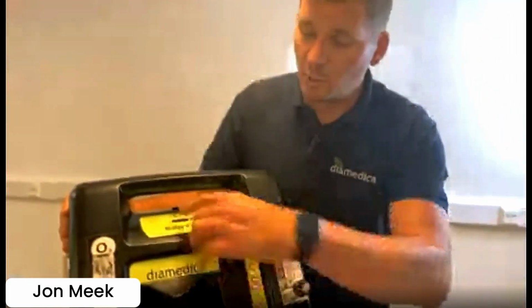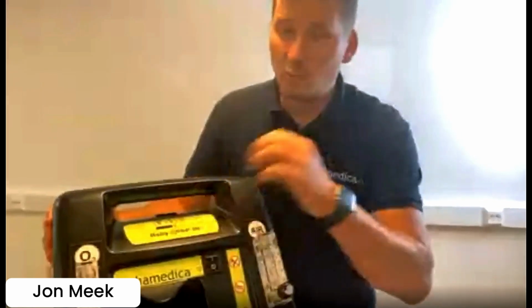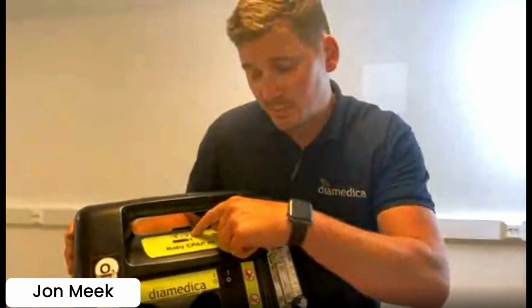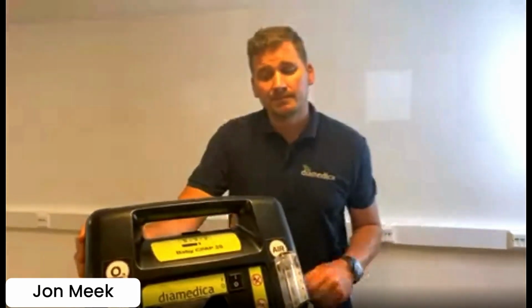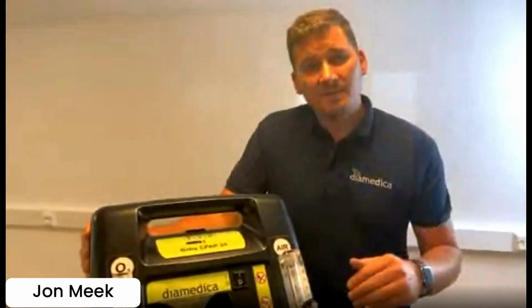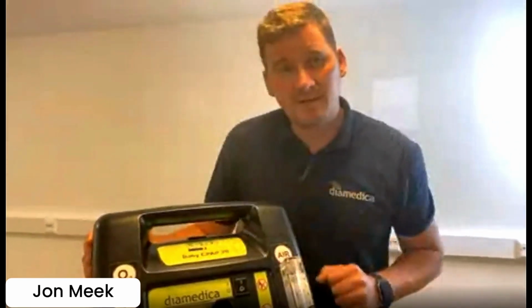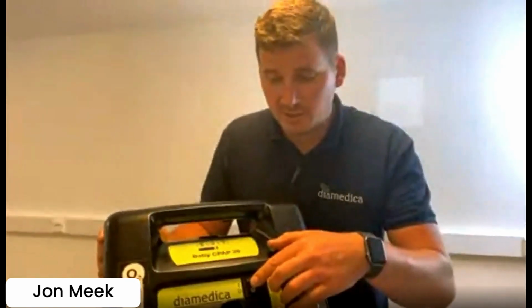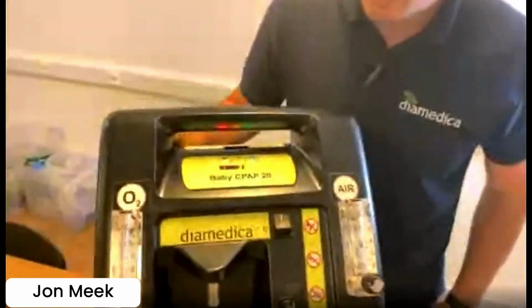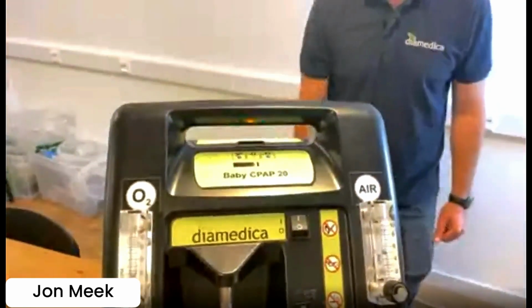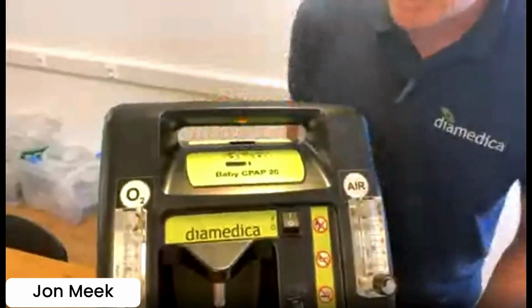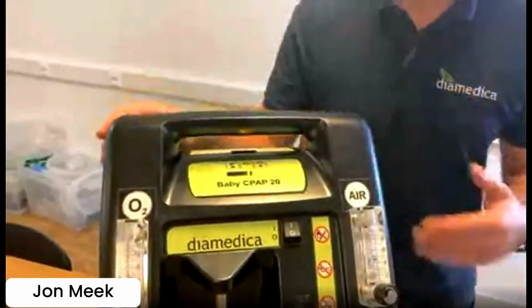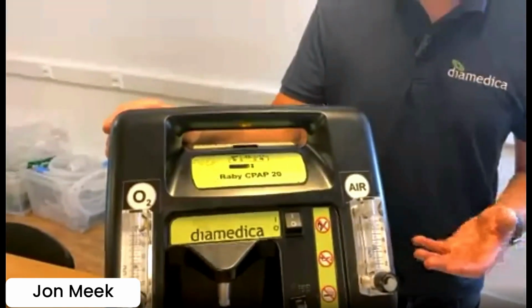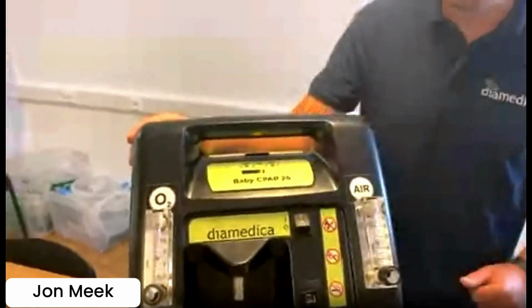So when I switch this on, what will happen is all 3 lights will come on, the alarm will sound for 1 second, and then what we'll see is we'll see the low oxygen light come on. And this will take approximately 5 minutes, maybe a bit less, for the green light to come on. And that is the key light we want to see to say the light's green, we're good to use the machine. Okay, so I'll switch the machine on. All lights come on and the alarm sounds. The low oxygen light is now on. So we know it's going to take a little while for it to build up and generate its own oxygen. So it shouldn't be used until the light goes green.